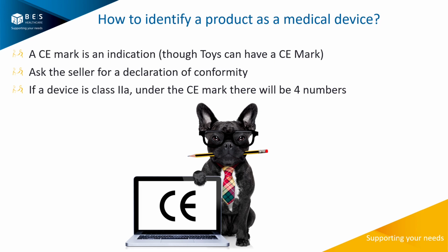So the best way to find out is to ask the seller for a declaration of conformity. This is in effect a certificate, a document which says this device is certified safe under these regulations, and it should be absolutely clear. Just as a small rule of thumb, if you're trying to identify whether something's class 2A or above, what you'll see under the CE mark is four numbers. This is what identifies the notified body, which is the organisation which looks over the application to be CE marked.